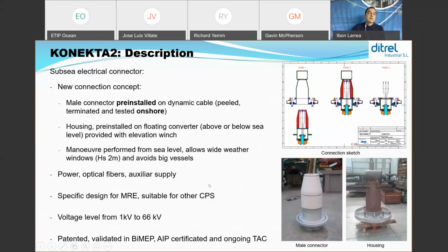This connector is ready for power, for optical fibers, for auxiliary supply. The design is specific for marine renewable energies and suitable for other off-the-shelf cable protection systems like bend stiffeners. It's suitable specifically for floating devices, although it could also be useful for non-floating devices. The voltage level goes from 1 kV to 66 kV.